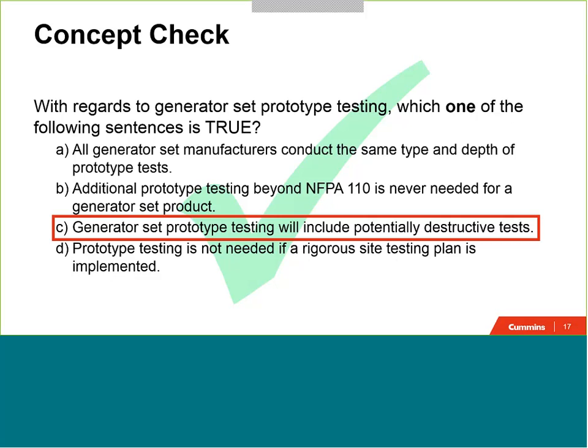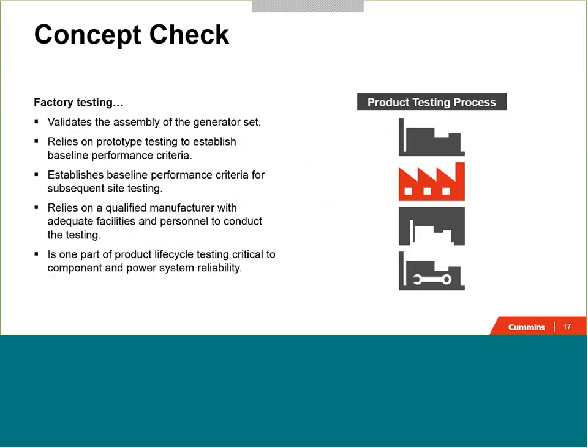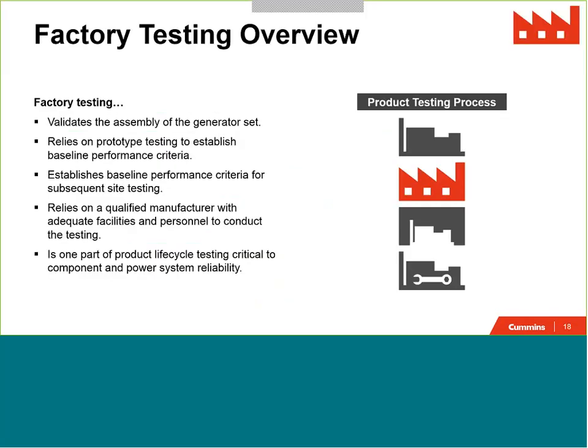With that, we're going to go ahead and move into factory testing. So factory testing, the big difference between prototype testing and these next three parts of the product testing lifecycle is that prototype testing is conducted on a prototype, whereas factory testing, site testing, and maintenance testing are all conducted on the actual product that is going to be installed on site. So factory testing, first of all, validates the assembly of the generator set in the unique configuration that you are going to receive it, or your client is going to receive it in.